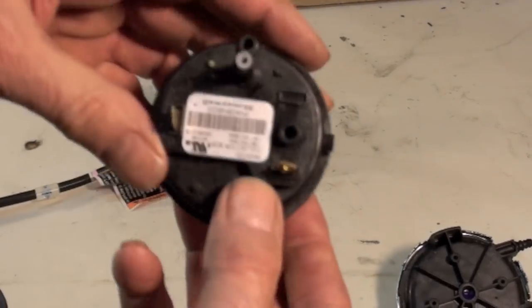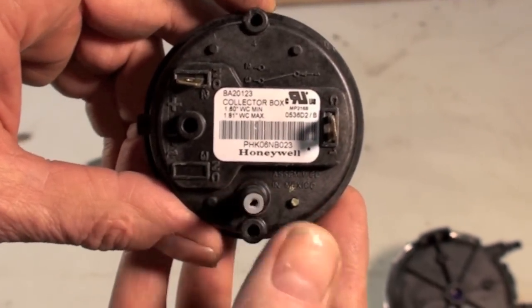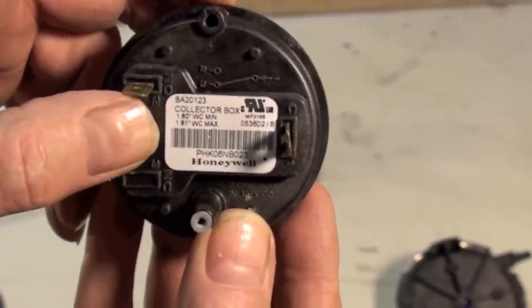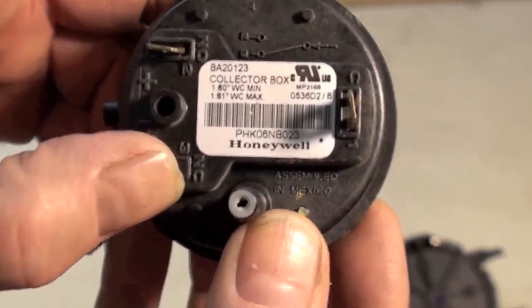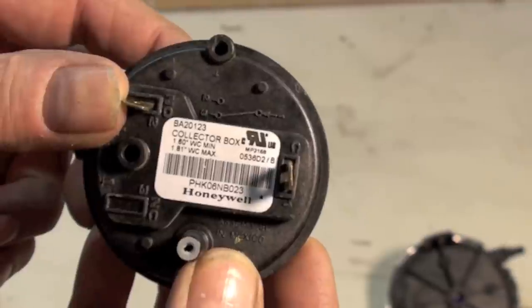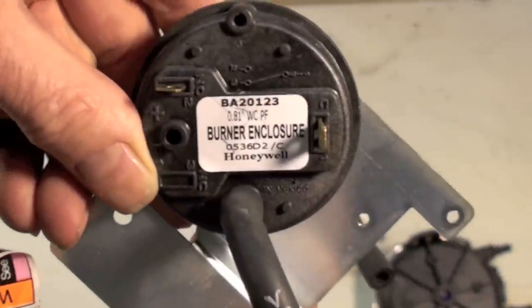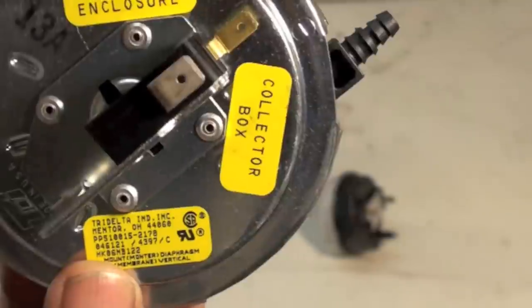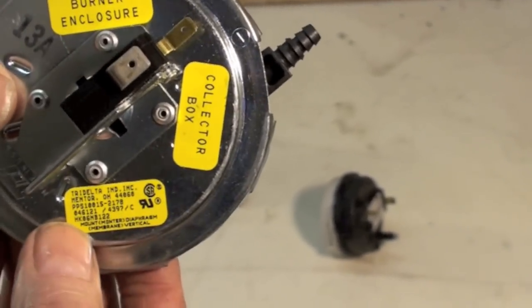Now, pressures that they run at. This one here is upside down. If you look at it, it says 'collector box' and then gives you a range of pressures: 1.6 to 1.81 inches of water column — it has to make between those pressures; any lower and it will not make. Here is another one that gives you 0.81 inches of water column. Some have numbers like that; some don't give you any numbers at all, and you'll have to go to the factory or a dealer to find out what the pressure should be.